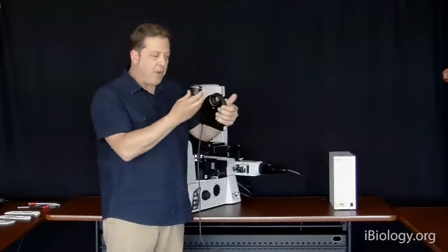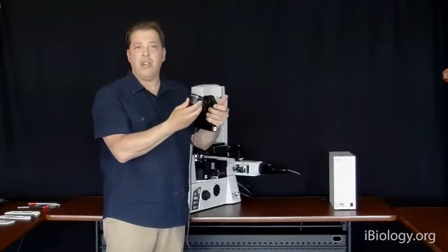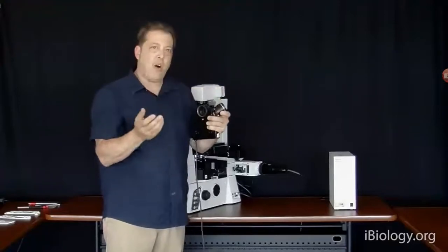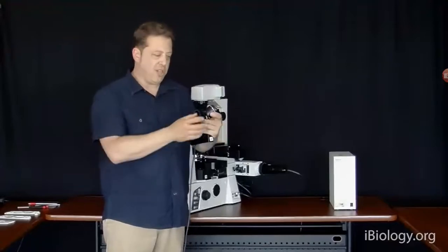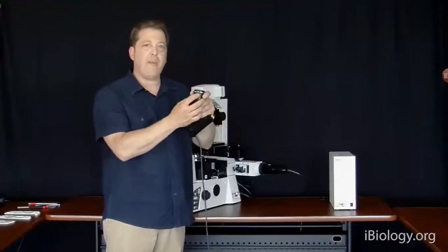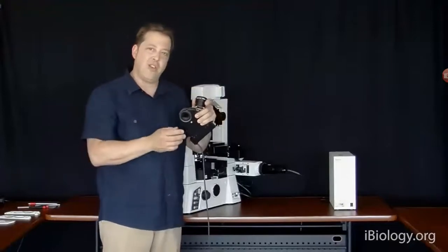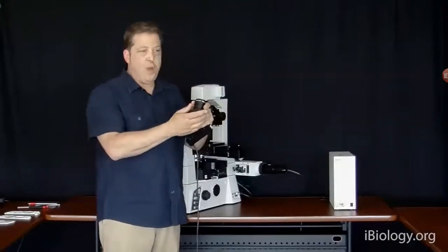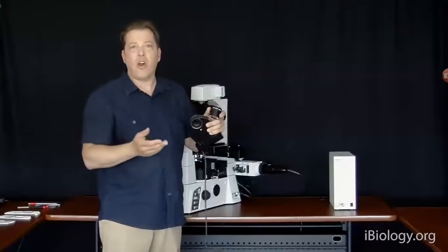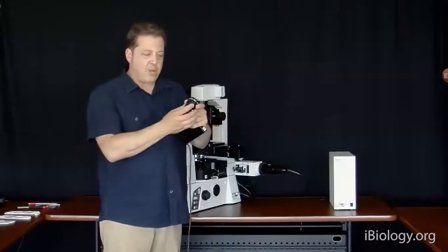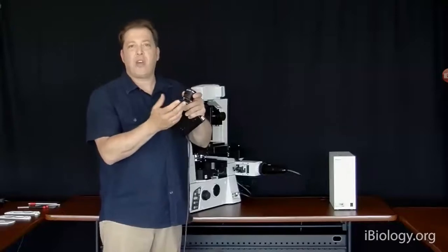And we can put multiple condenser lenses on this, always trading off working distance versus resolution. So if we have 0.52 numerical aperture, it's going to significantly limit the resolution in transmitted light that you can get with, for example, a 1.4 NA oil immersion lens. That's why we make several different compromises.